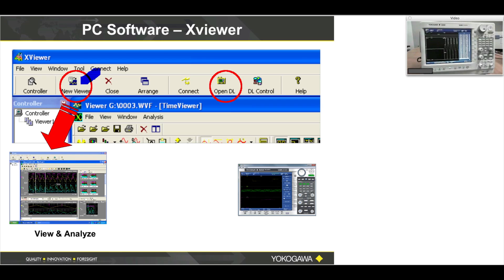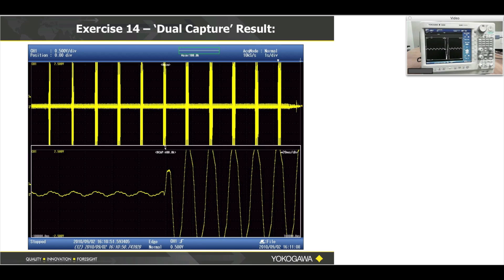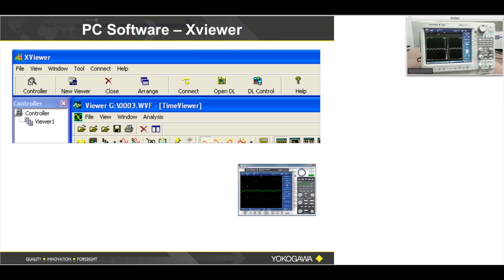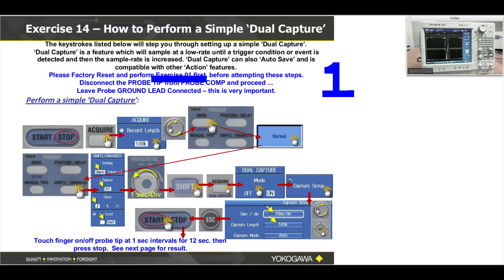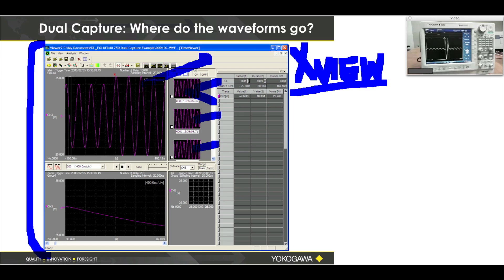Each of those events would be viewable at high sample rates within X-Viewer. The idea with dual capture is that when you open this file as a binary file, you'll have these events listed in X-Viewer as separate entities. You can examine those separately and at very high sample rates. I hope I've impressed upon you the power of it. In the X-Viewer window, there's a zoom window at the bottom — you can turn that off or on.